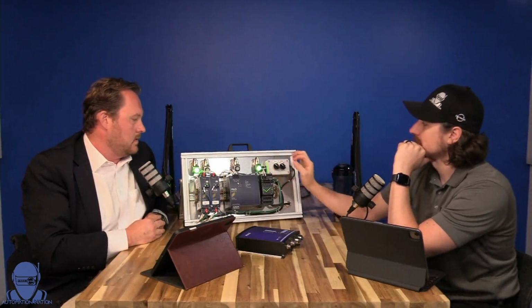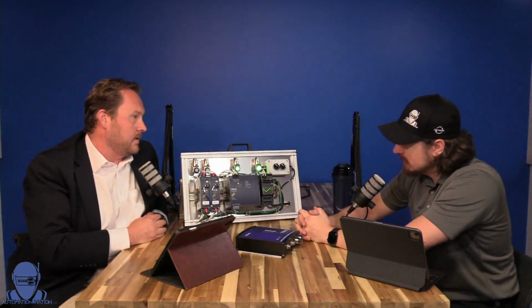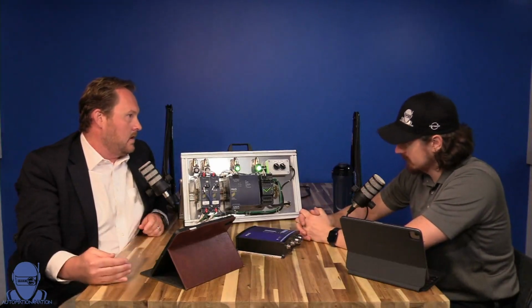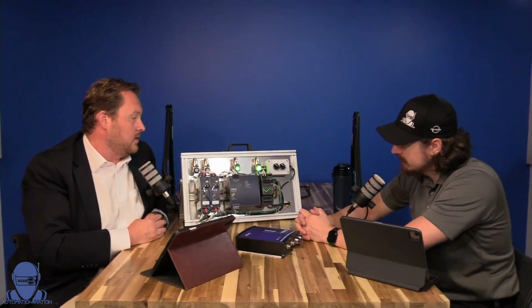So both of them off—basically the equivalent of unplugging this board. The critical load did not flicker in any way, and that pilot light that just came on is simulating the DC UPS system. So even if you lose both power supplies or the AC feed coming into both redundant power supplies, you're still going to get enough time to safely shut down.